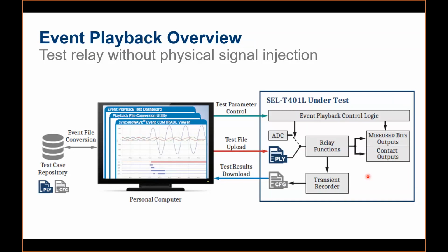Apparently, no, because just for one element, that is the traveling wave differential element, we use a direct fiber. We need a direct fiber between both relays. So what we support now is up to 200 kilometers for that particular element. All other elements, you can achieve through multiplexers and other things. So there is no practical limitation for other elements. But only for TW87, the differential element that's based on traveling waves, you should take care about the line length. So 200 kilometers is the limit.